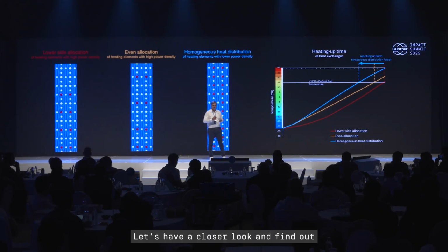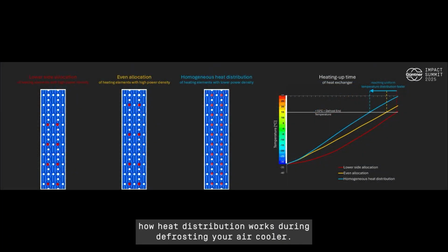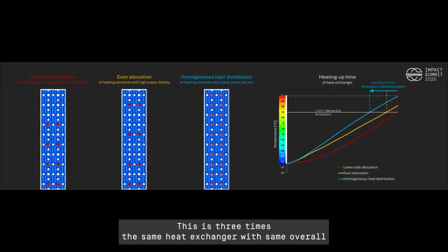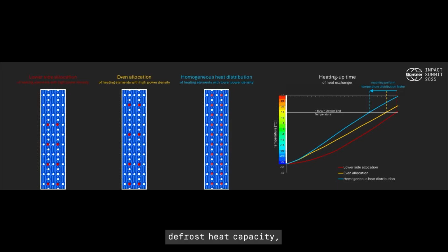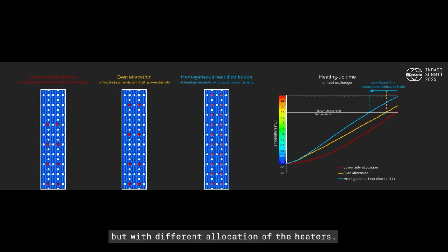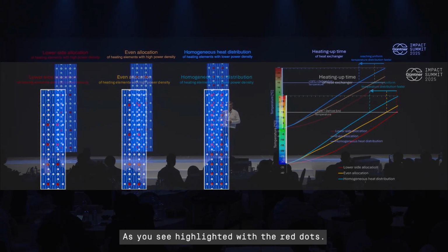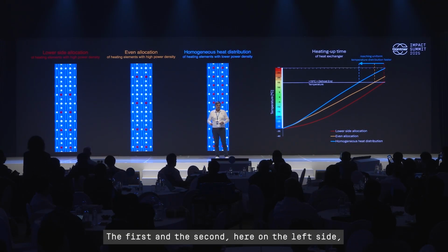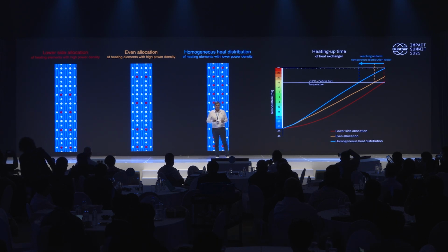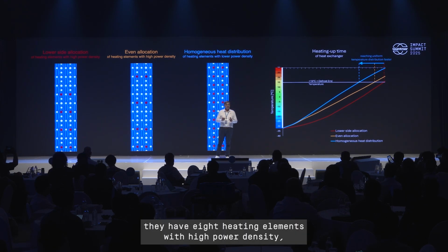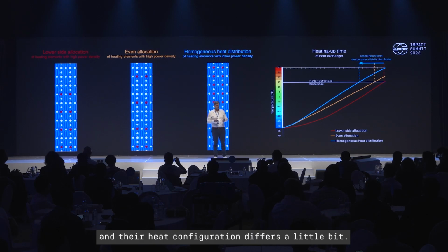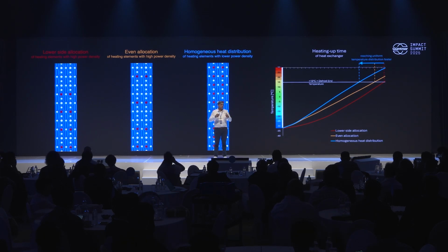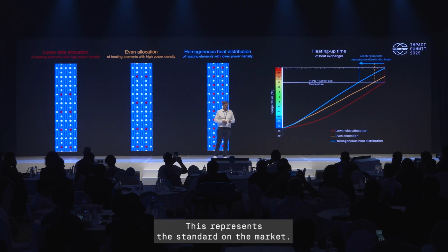Let's have a closer look and find out how heat distribution works during defrosting of your air cooler. This is 3 times the same heat exchanger with the same overall defrost heater capacity, but with different allocation of the heaters, as you see highlighted with the red dots. The first and second, here on the left side, have 8 heating elements with high power density, and their heater configuration differs a little bit. This represents the standard on the market.